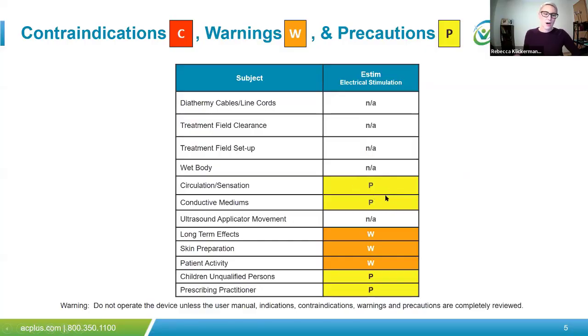Conductive mediums are also listed as precautions. The use of conductive mediums such as gels and lotions is not advised if they're not provided. So the oval electrodes for the head and neck PENS protocols have that hydrogel on the back, so you should not require any additional type of medium, and it's not advised to pair additional ones as well. The long-term effects of e-stim are really unknown, and that's why it's listed as a warning. Skin preparation is also listed as a warning.